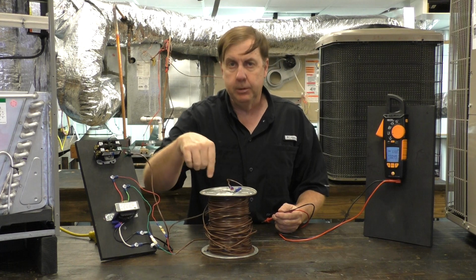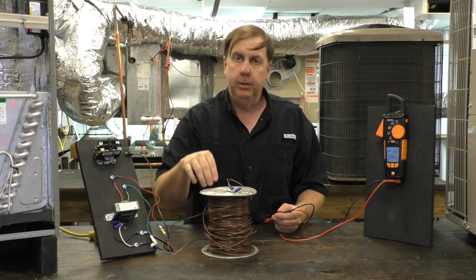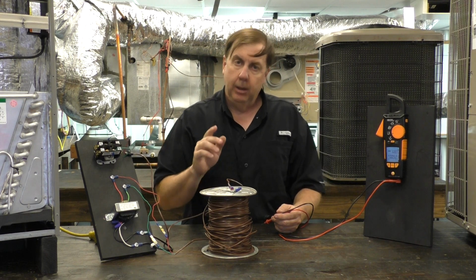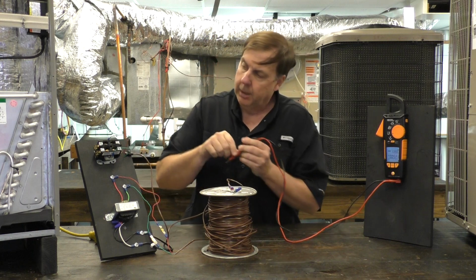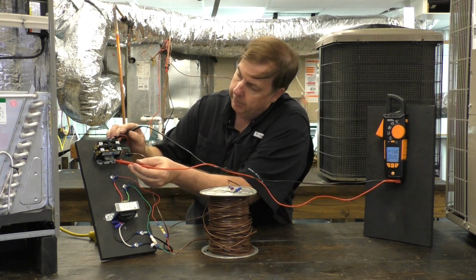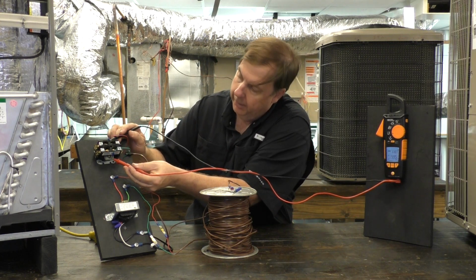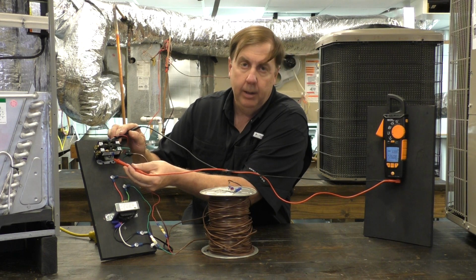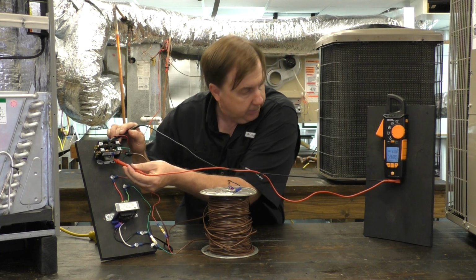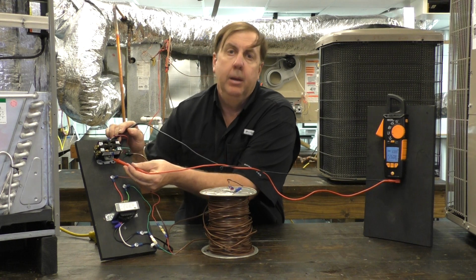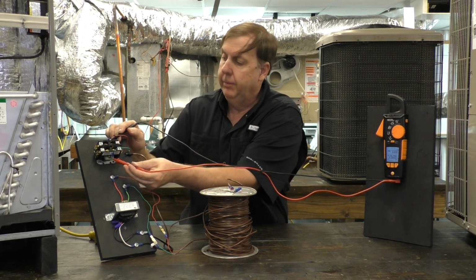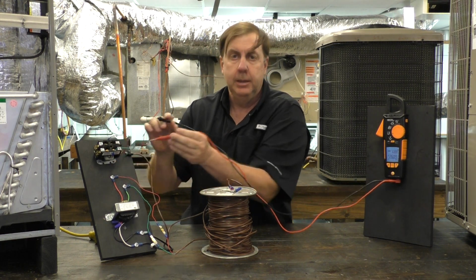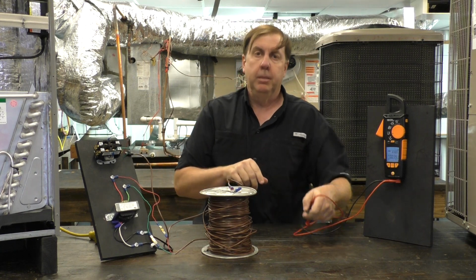Then it travels through this wire. 500 feet of wire it had to travel through. Although it's big wire, it's still going to drop our voltage a little bit. So if I measure it on the secondary after it goes through the wire, as it finally gets to the contactor, you can see it's dropped down a volt. So now we've got 26 volts. Not significant here, but it proves my point.